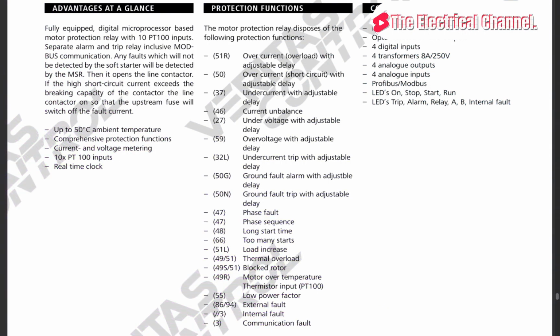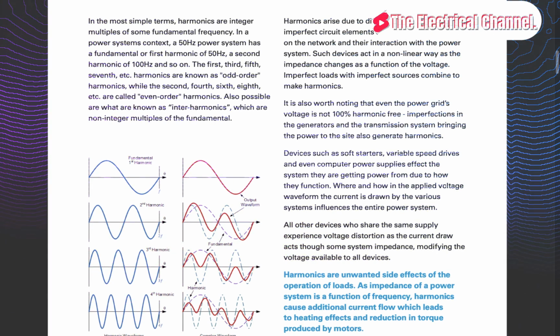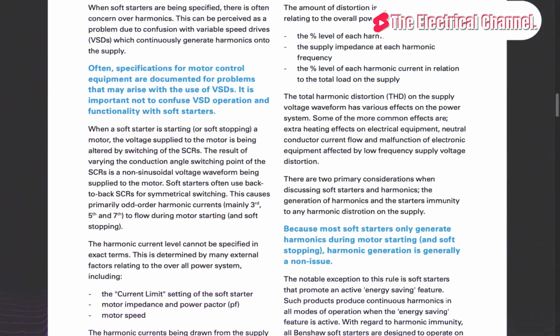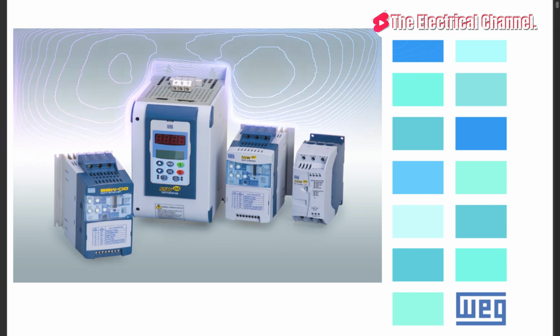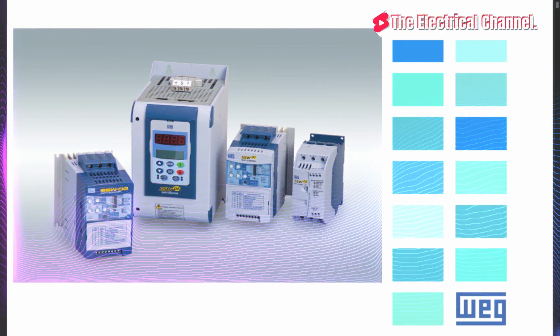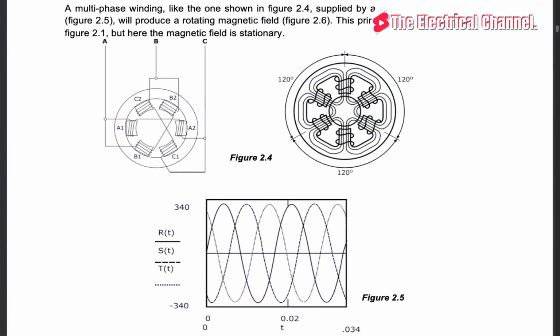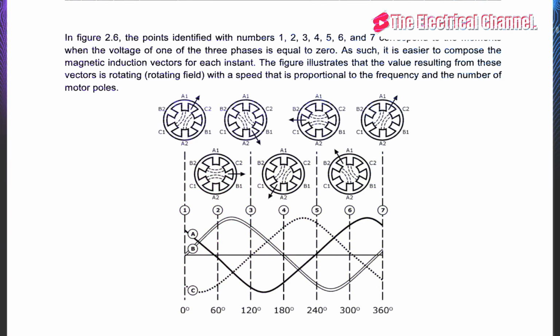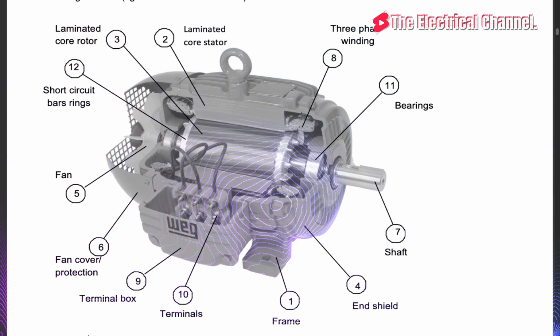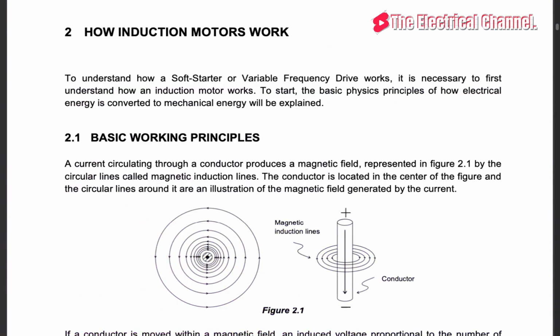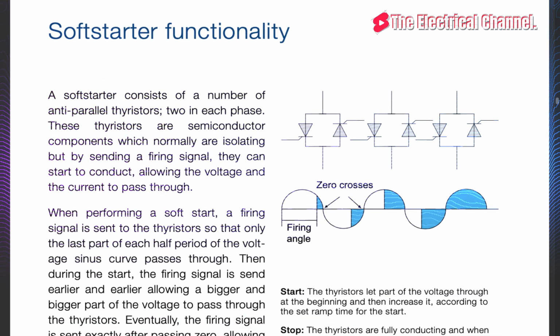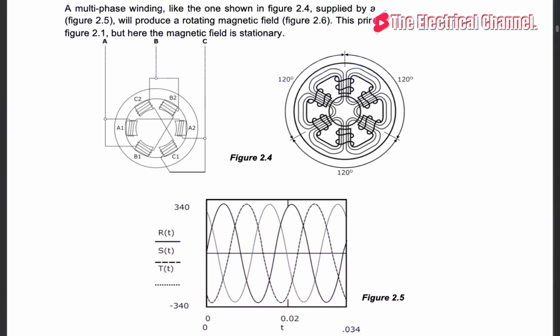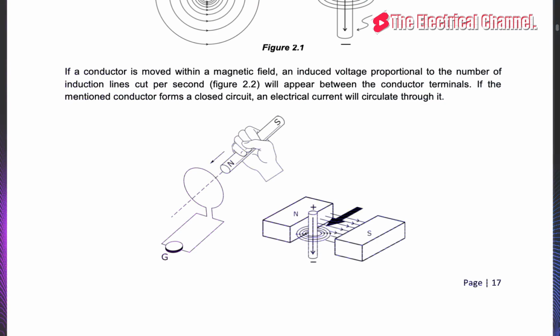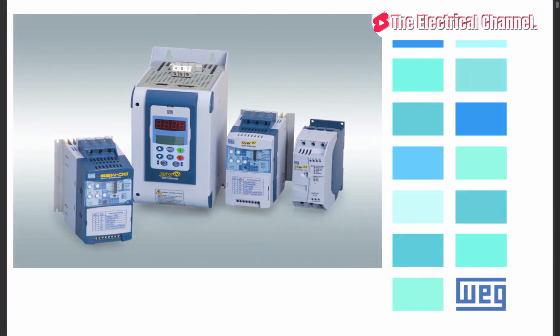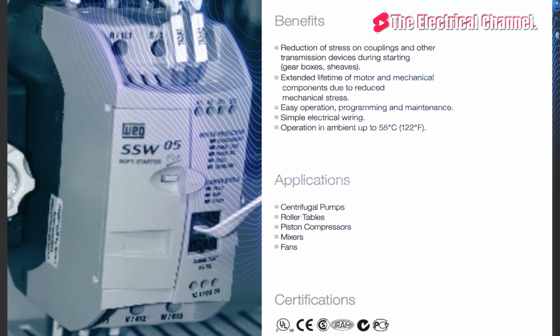Initial voltage. Initial voltage is sometimes named pedestal voltage. This is the point from where the soft starter starts to ramp up. The torque of the motor will drop with the square of the voltage. If the voltage is set to, for example, 20%, the starting torque will become 0.2² = 0.04, or 4% only. And the motor will not start from the very beginning. Therefore, it is very important to find a level that is just high enough to make the motor take off directly to avoid unnecessary heating.